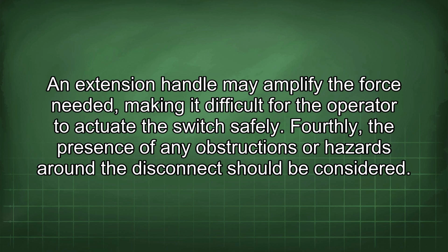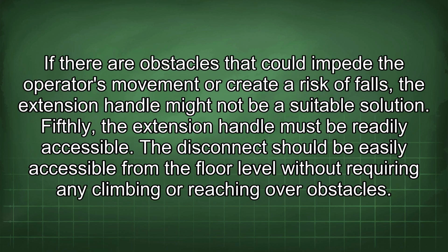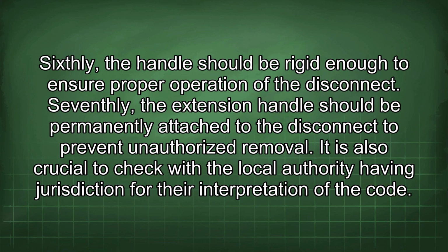Fourthly, the presence of any obstructions or hazards around the disconnect should be considered. If there are obstacles that could impede the operator's movement or create a risk of falls, the extension handle might not be a suitable solution. Fifthly, the extension handle must be readily accessible. The disconnect should be easily accessible from the floor level without requiring any climbing or reaching over obstacles. Sixthly, the handle should be rigid enough to ensure proper operation of the disconnect. Seventhly, the extension handle should be permanently attached to the disconnect to prevent unauthorized removal.